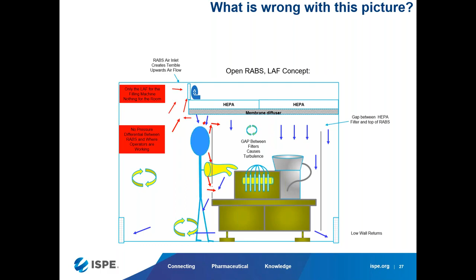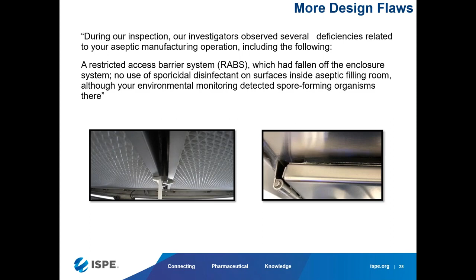This is another very common scenario. During our inspection, our investigators observed several deficiencies related to your aseptic manufacturing. The RABs had gaps in the enclosure systems. You know, these gaps, these are an easy fix. We see this all the time. You tell me, when you do cleaning of your RABs, can you go inside and clean these gaps between the HEPA filters? You can't. There are simple solutions. And this kind of design then leads to eddy currents in smoke studies, which FDA is catching very fast nowadays, right? Plus, it can start contamination, spore-forming organisms, because you can't clean those gaps.